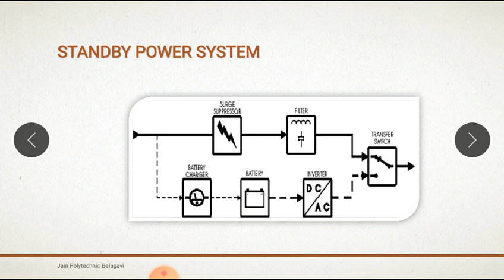The inverter is used to convert DC to AC power to support the load when the utility fails. Normally the inverter is in standby mode, keeping the batteries charged. Should the utility power go out of specification, the inverter powers the load, drawing energy from the battery. This is typically called single conversion, because at any point of time the power is only being converted once. Next we'll move on to the online UPS system.